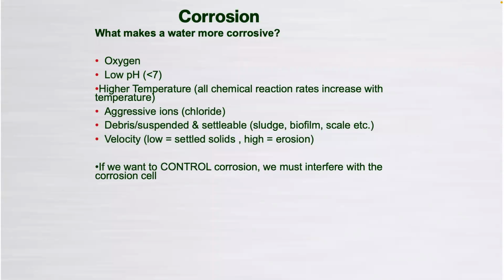So if we want to control corrosion, we must interfere with the corrosion cell. So either we remove the water, which we can't do, it's a hydronic system, or reduce the amount of oxygen that is in our water. So we can use various types of mechanical means. We can use air separation, which removes free air or microbubbles. And if we want to remove dissolved oxygen from the water, we can use pressure step degassers, which essentially use Henry's law. They take a small volume of water at a time and reduce the pressure. The dissolved oxygen comes out of solution and is released out of an air vent, and then that water's pumped back into the system.